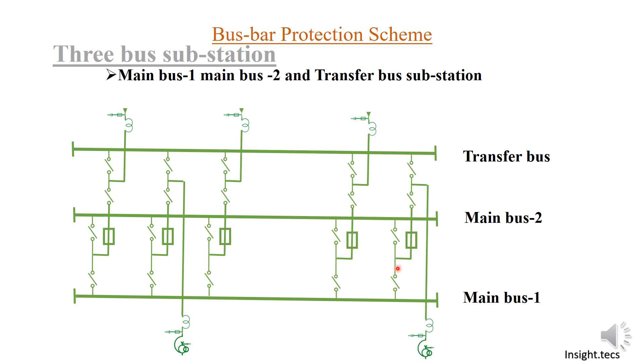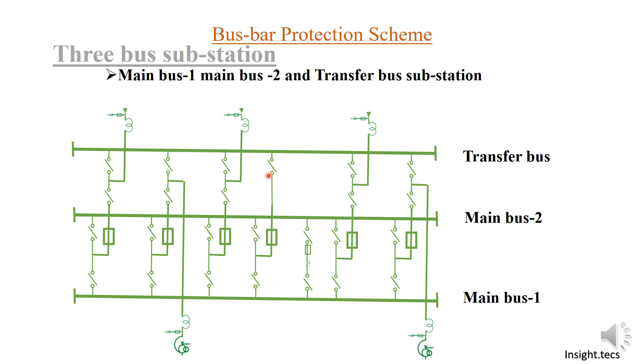Similarly, the outgoing transformer feeder will have one more isolator along with Main Bus 1 and Main Bus 2 selection isolators. A bus coupler is always present to maintain power supply between Bus 1 and Bus 2 in case of any emergency. What is different here is that a Transfer Bus Coupler (TBC) is also present in this scheme, playing a very crucial role. Along with the bus coupler, there are two isolators, one circuit breaker, and one additional isolator for the transfer bus.